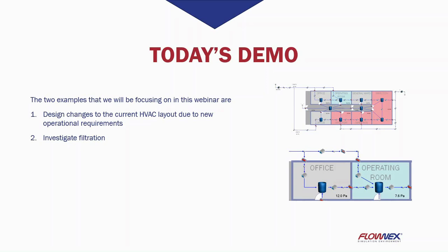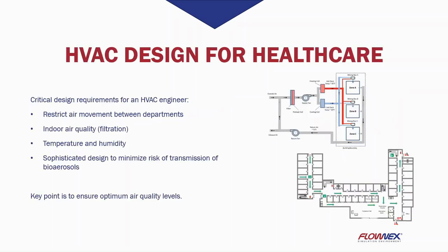Willie, could you kindly explain the first example so that we can get an idea as to where Flownex fits into the HVAC design process? Yes, Marinus. So some of the critical design requirements that an HVAC engineer must attend to for a healthcare HVAC design is to restrict the movement of air between departments. This will largely prohibit the spread of bioaerosols and decrease infection rates.